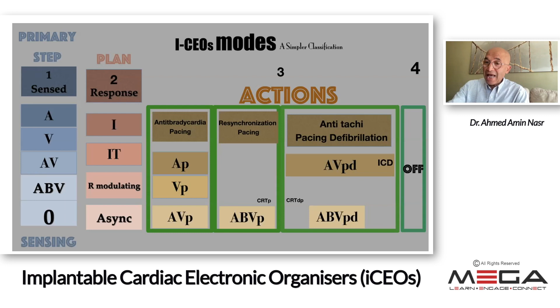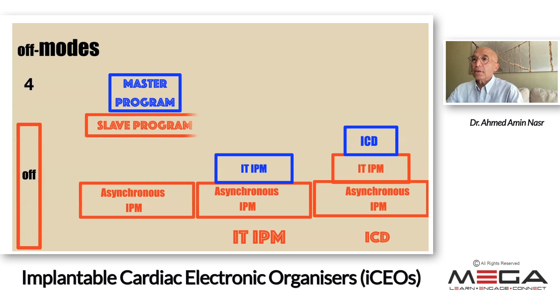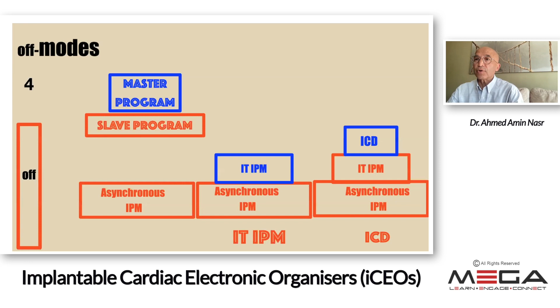Now, the off mode. Asynchronous IPM did not live long enough, as R on T was too intimidating. Sensory, function, and IT IPM response were added as a master program, while asynchronous pacing became a shadowy slave backup program. ICD master program joined the pack, and IT IPM became its slave program that would work in case of failure or stopping. So there is always a master program and slave program. And guess what? If you shut off the master program, you would find that the slave program is unleashed and in action. Now, let us shut off the IT IPM.